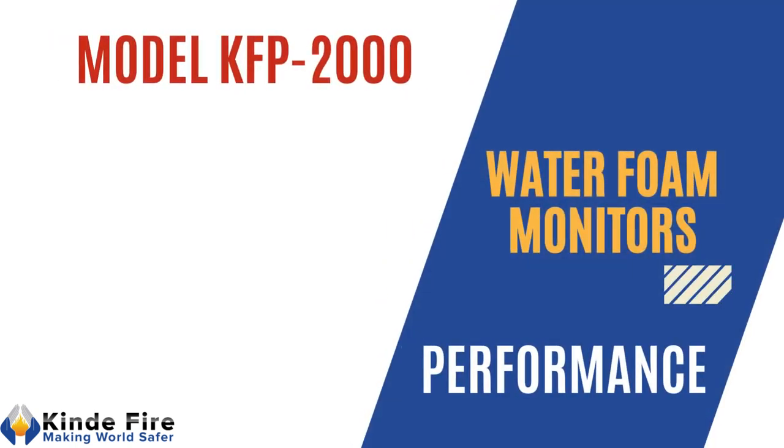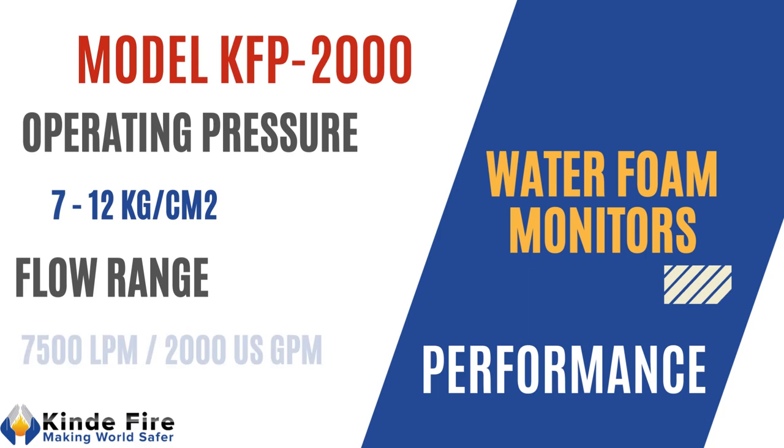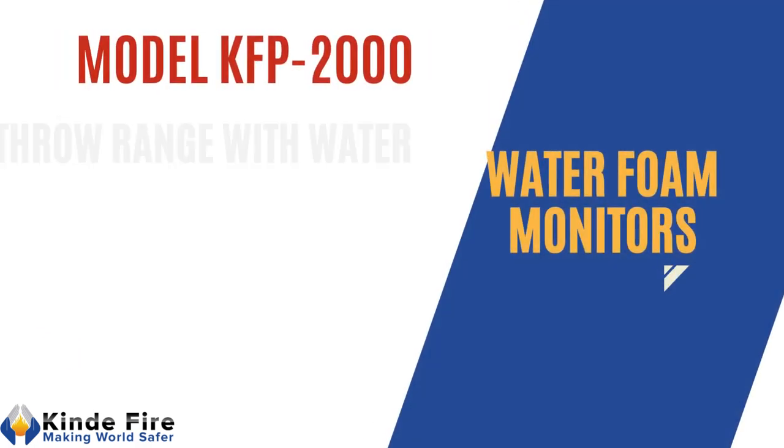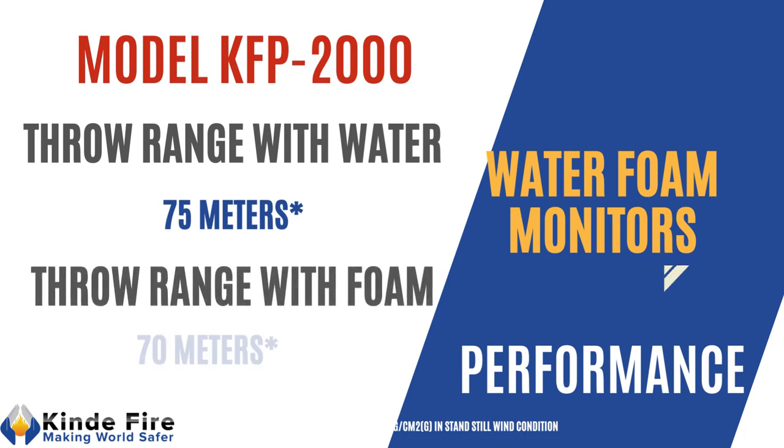Model KFP2000: operation pressure shall range from 7 to 12 kg per cm². Throw range with water shall be minimum 75 m and throw range with foam shall be minimum 70 m. Flow range with water shall be minimum 7500 LPM.